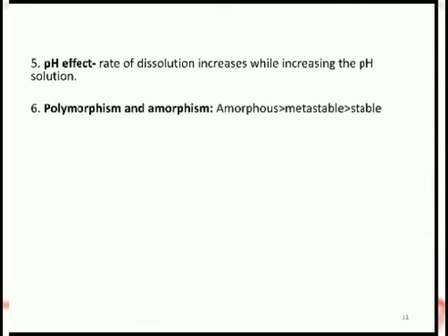The dissolution fluid is either water, buffer solution or dilute hydrochloric acid, that means HCl, solutions simulating the gastric pH. The dissolution fluid is maintained at a temperature of 37 degrees Celsius.